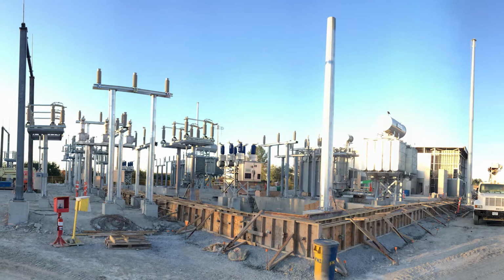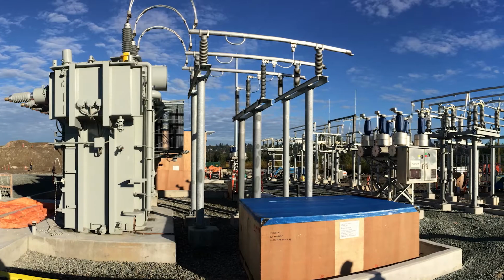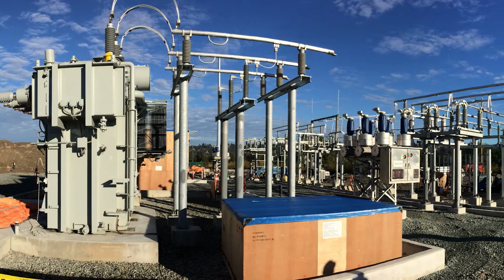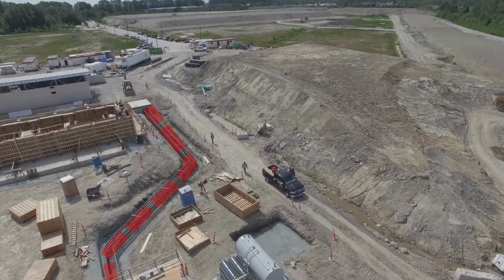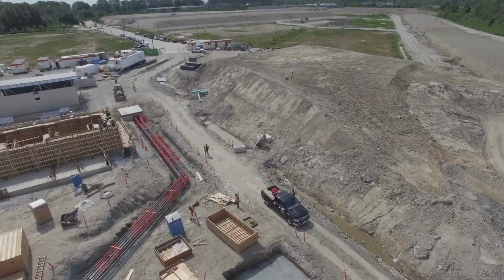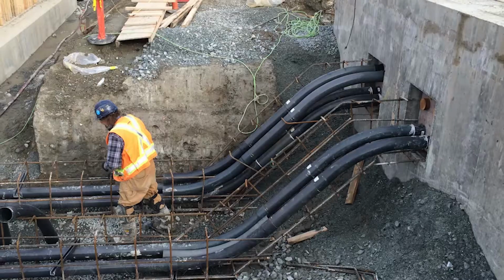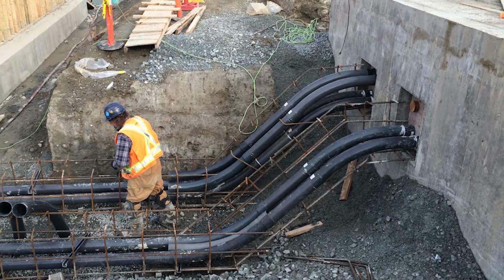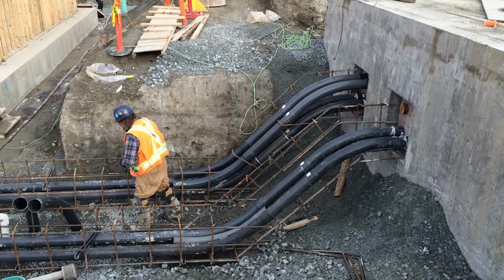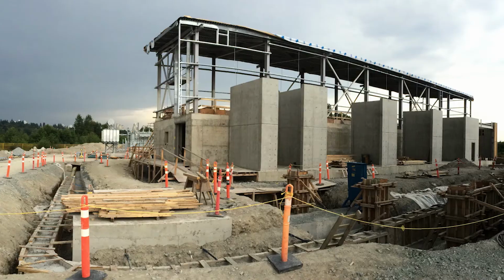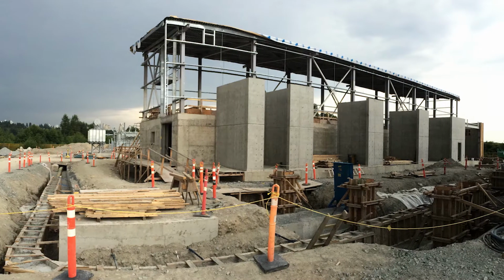The 25 kilovolt side of the transformer fed the gas-insulated switchgear building through underground 2,000 MCM cables encased in concrete duct banks. Duct banks serve as an underground pathway for the substation's power cables. The duct banks contained as many as 16 5-inch conduits each.